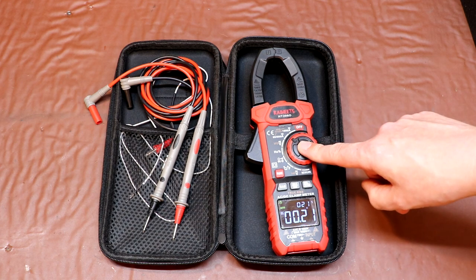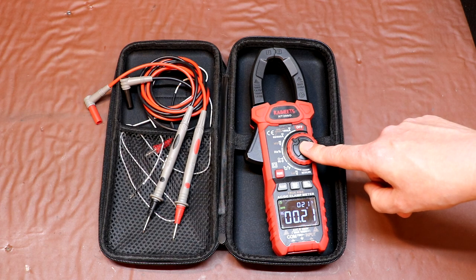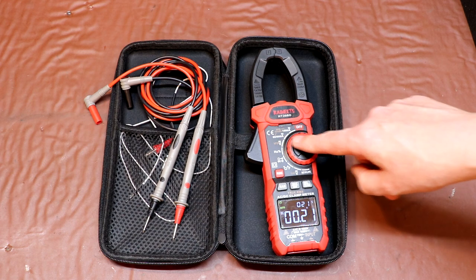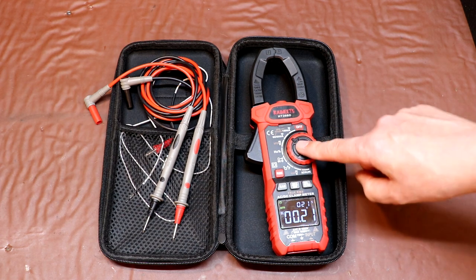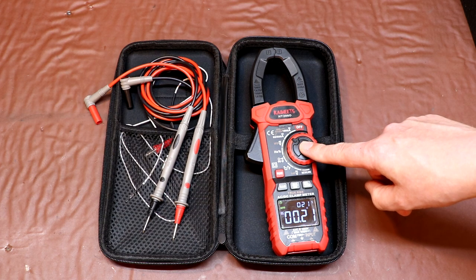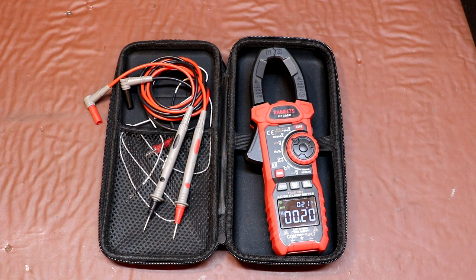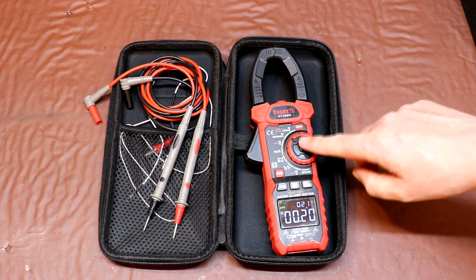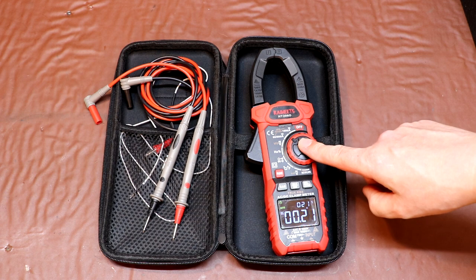So I think the most likely people to purchase this are probably still people that are interested in domestic type installations, and basically this current range is a little bit too high, and I certainly would have appreciated the ability to actually measure very low currents to find faults like earth leakage faults. And you would also find that most lighting circuits are now using LEDs as opposed to the old-fashioned incandescent lamps, and these LEDs only draw a small amount of current, so the fact that this meter doesn't read anything below 100 milliamps, well, I think that could be a problem for some people.